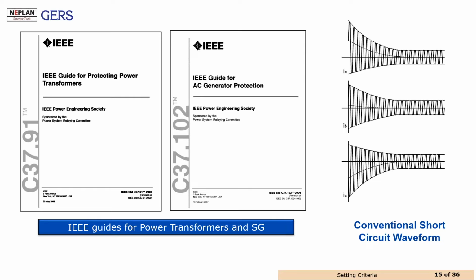We have here some standards that are highly used for the protection of the transformer and synchronous generators. These standards are still used, since we find this kind of power elements in the electrical networks, and surely we will continue finding them. However, these standards are based on the conventional theory of short circuit, which typically comes from synchronous machines or from turbo machines, and this behavior was considered for these standards.